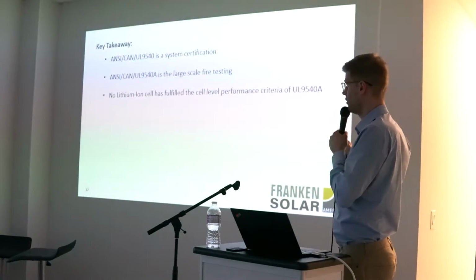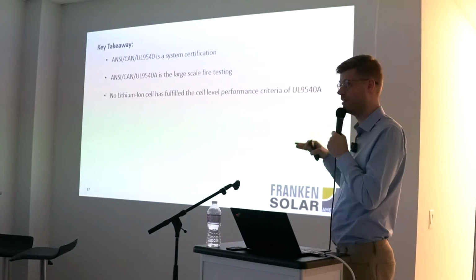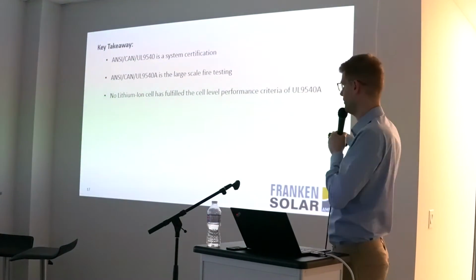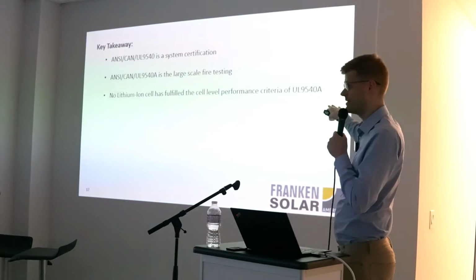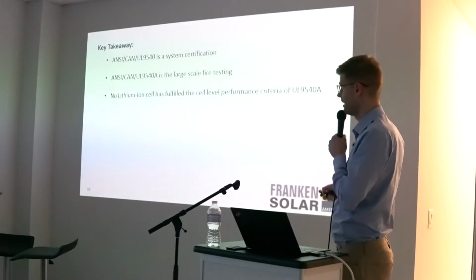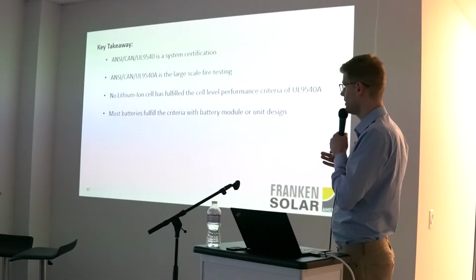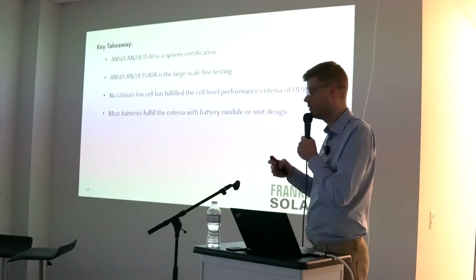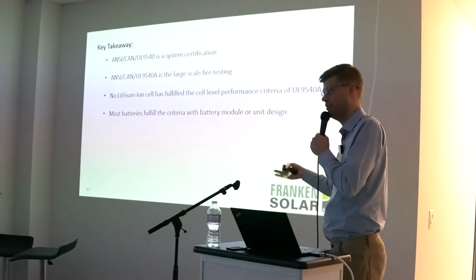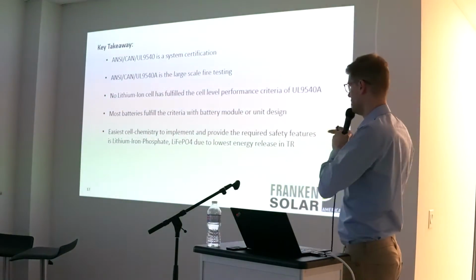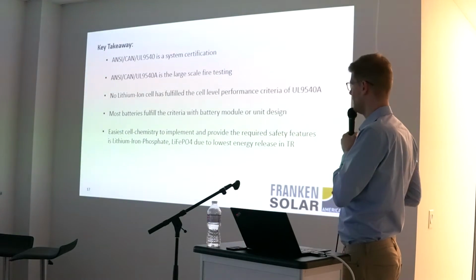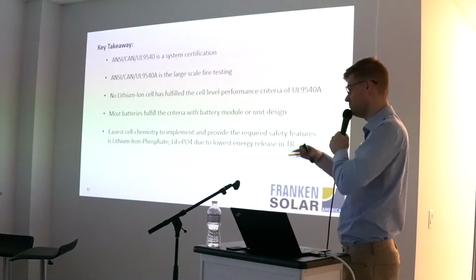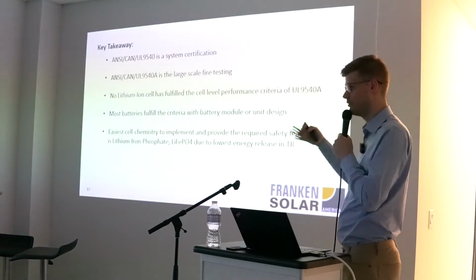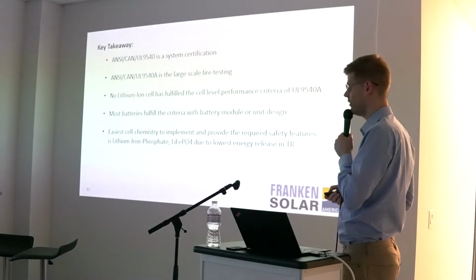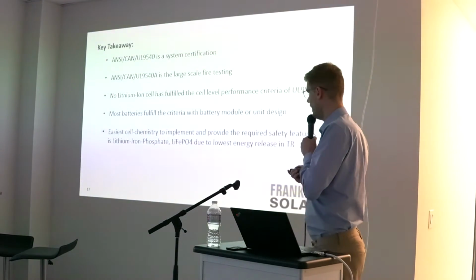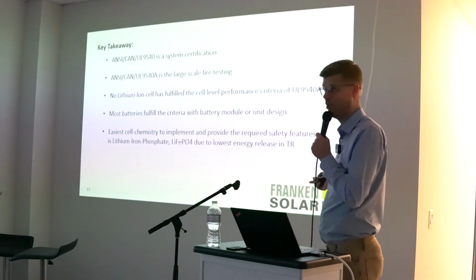Not a single lithium cell currently on the market has fulfilled the cell level requirement, and that's important later on when we get to the second half of this presentation, that actually passes the requirements of UL9540A. And then most batteries fulfill the criteria if you put that cell into a module, or then the module in a unit and have it in that contained environment. And the easiest cell chemistry to do that without adding more and more safety level, and of course cost, to the system is lithium iron phosphate, so an LFP battery, and they have the lowest energy release rate in a thermal runaway condition.